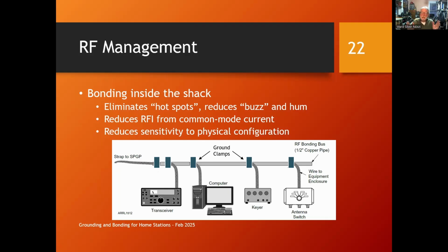So what does this do for you? By connecting all this stuff together, you eliminate these hot spots. We've all had that experience, that fun experience of touching our nose while we're transmitting with a metal microphone, and suddenly you get an RF burn. That's a hot spot. It's a high voltage spot. And we want to minimize high voltage spots. We want everything to be at the same voltage, no hot spots. So we bond everything together.